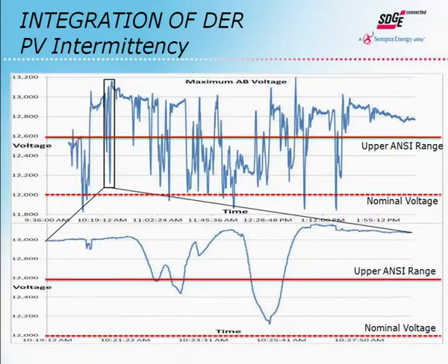With this change in the PV system, we're actually moving that voltage around significantly, and our regulation equipment is operating much more frequently. It tries to follow and correct this curve, but it has a 45-second delay, so by the time it knows to move, the PV system has come back up, and now it has to move back into its regular state. You can imagine the additional operations this causes. The challenge for a utility is that these additional operations drive additional costs and O&M, since we'd have to replace this voltage regulation equipment much earlier than we otherwise would have.